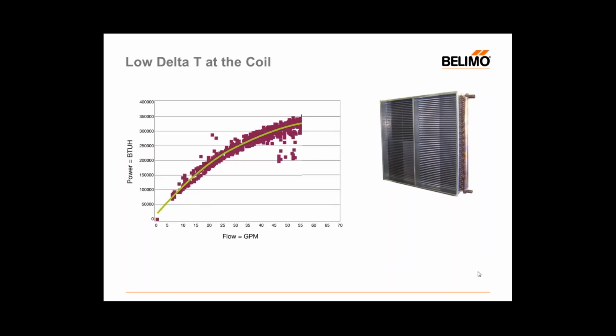To understand exactly how this comes into play, let's take a look at the performance of a typical heat exchange coil. So we'll just call this an air handler coil. In this case, we're looking at a chilled water coil, but we would have a similar performance on a hot water coil as well. So what we're looking at here across the x-axis, we're increasing the flow through that coil. And then on the y-axis, we're increasing how much power, or BTUH, is produced by that coil. And you could see a few things that are noteworthy about the performance of a coil. One is that at low flows, 5 to maybe 20 gallons a minute, this curve is quite steep in comparison to where it is later on in its flow. And what that is an indicator of is that heat is being transferred more efficiently. So small increases in flow create larger increases in the amount of heat that's exchanged.